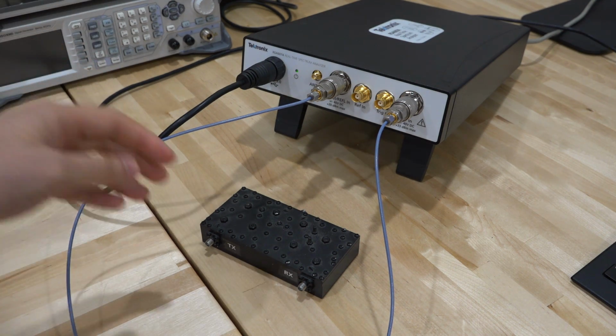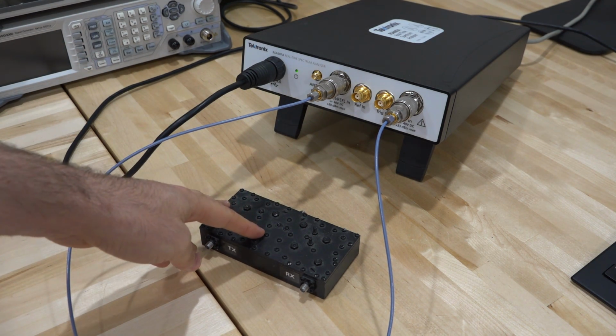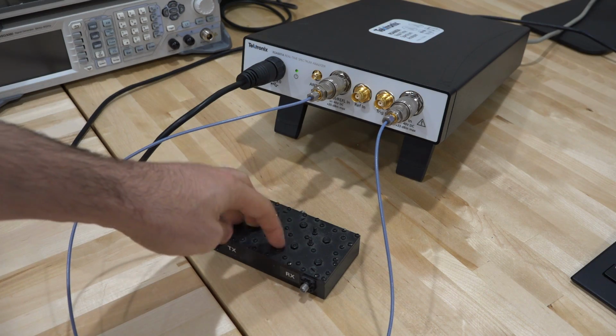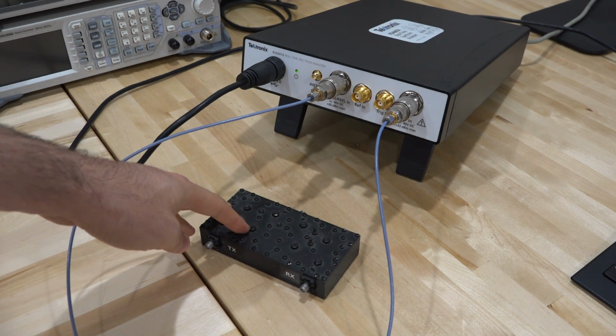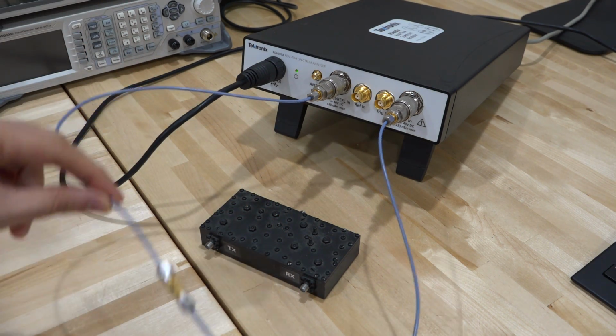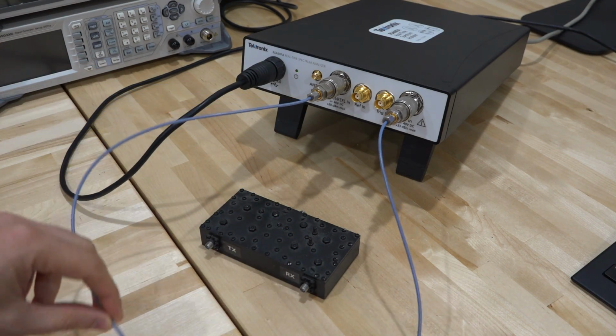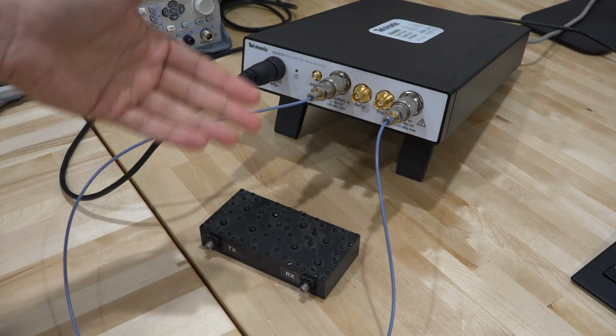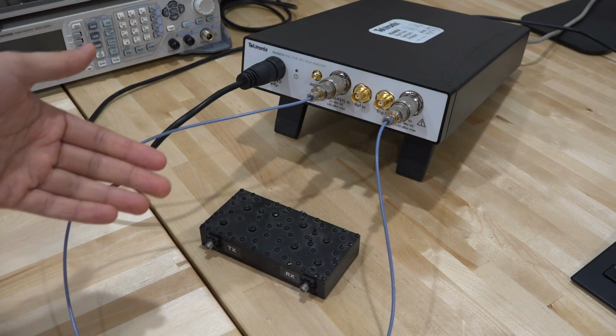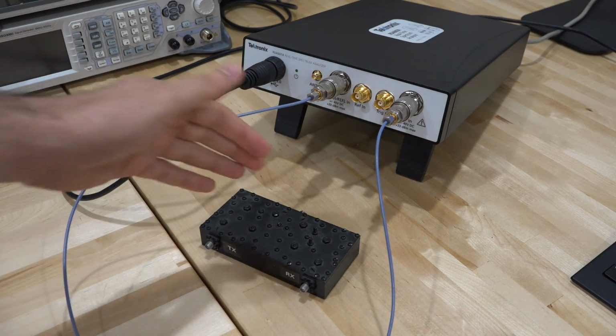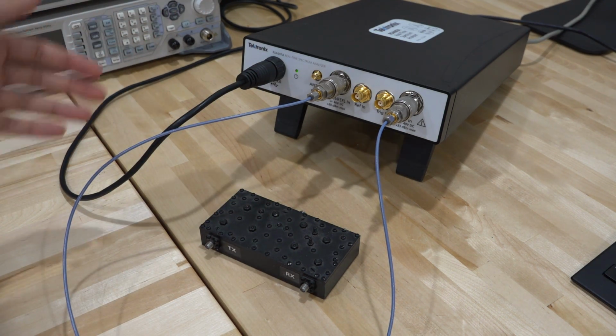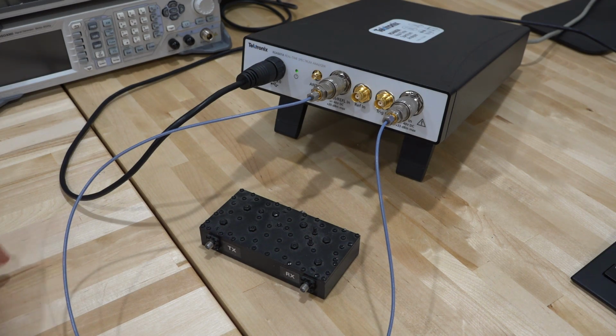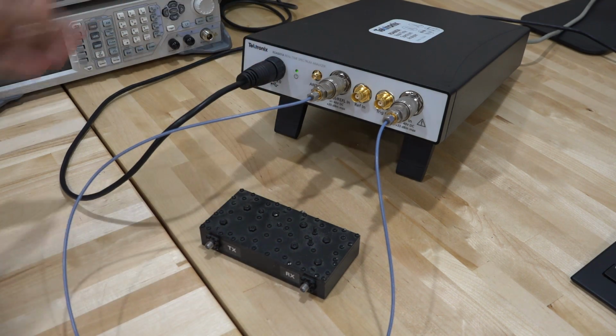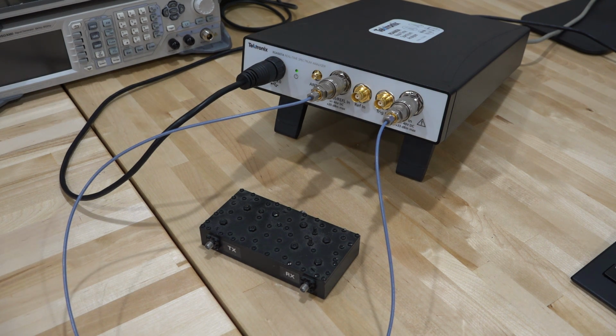Now with the tracking generator, we can send signals to various ports and see what the exact frequency response of this instrument is, and from that we can make some conclusions. Now to start, I put a through between the two ports, and this allows us to calibrate the instrument first for zero reference power, and then from then we can go ahead and measure this. Now before I do that, I want to show you a couple of settings that we can do on the SignalVu software to configure the tracking generator itself, along with a couple of different limitations that I hope they can remove in the future.